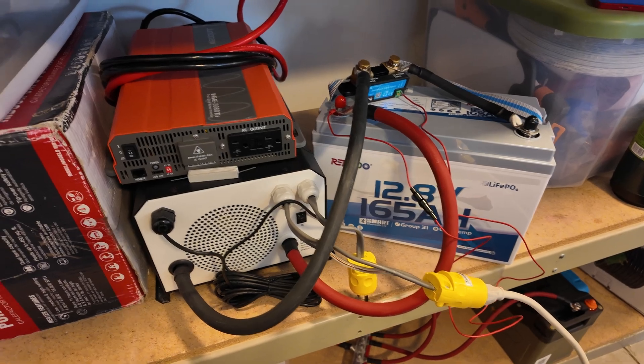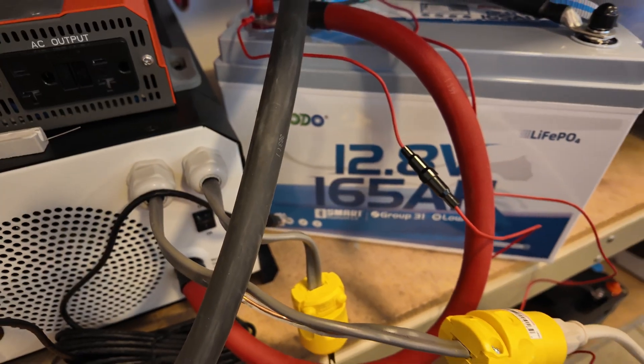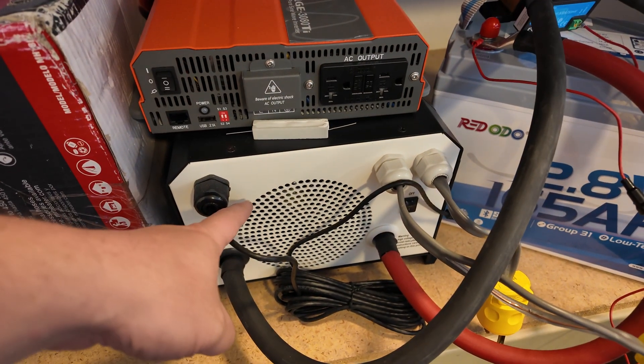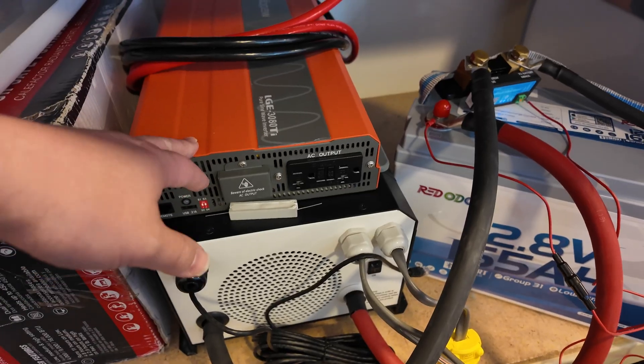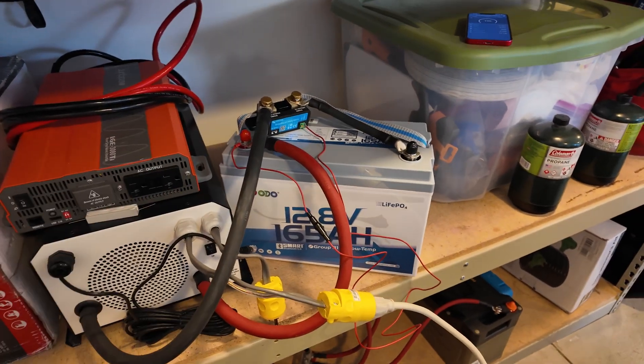Welcome to the high amperage testing. Here's a little test bench setup: the Redodo 165 amp hour battery is hooked up to this big 3,000 watt low frequency inverter. I have another 3,000 watt high frequency inverter right here that we can pair up if we need to push it even harder.